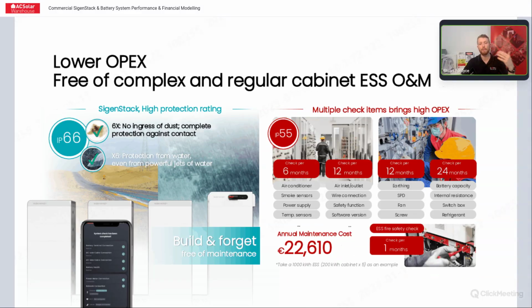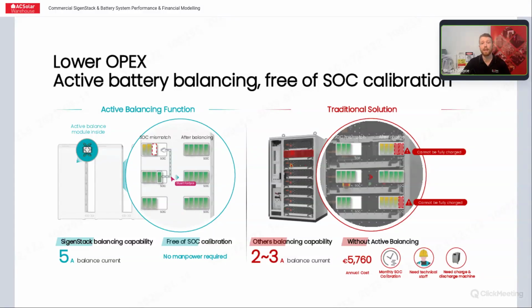They have temperature sensing across the entire unit. They have smoke detection within every single module. They have individual cell monitoring as well, like we'll go into here. The active balancing of cells allows every single cell to be managed individually. So these are things that can save you general ancillary costs when you're quoting up projects. And the ongoing maintenance costs can really stack up, especially if you're talking remote sites. So anything that can be done remotely from native hardware is a real bonus.